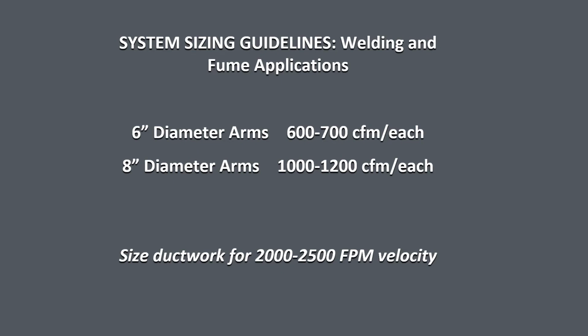For the ductwork sizing guidelines, we're going to use 2000 to 2500 feet per minute conveying velocity, similar to the exhaust we see for vehicle exhaust. We want to capture the contaminant, keep it in our airflow, and expel it where we want it expelled.